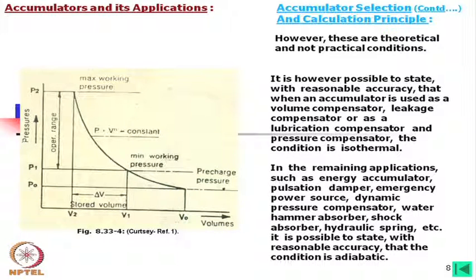For the remaining applications — such as energy accumulator, pulsation damper, emergency power source, dynamic pressure compensator, water hammer absorber, shock absorber, or hydraulic spring — it is reasonable to state that the condition is adiabatic, meaning a very quick process is occurring.